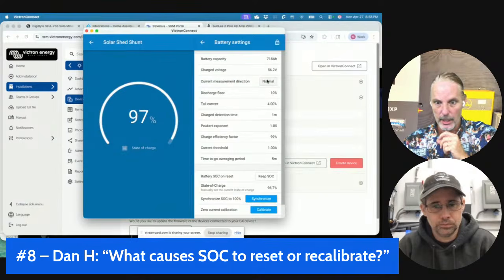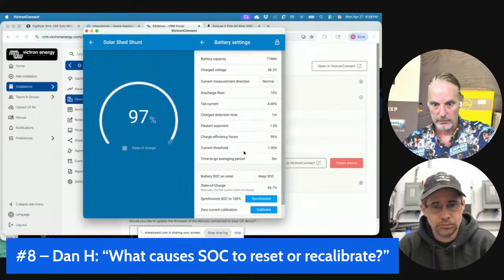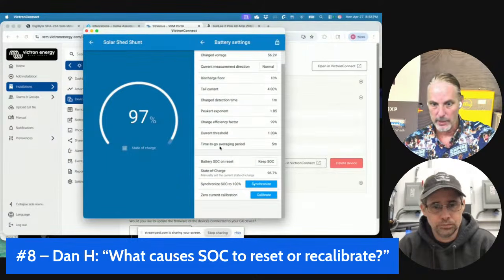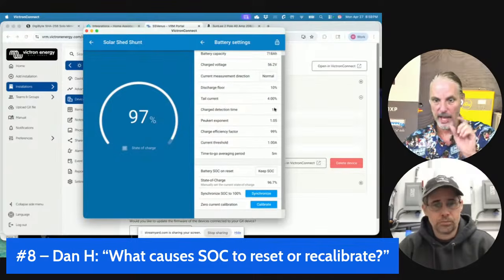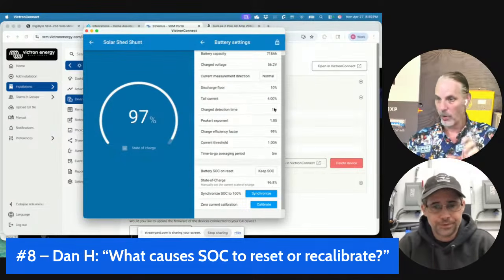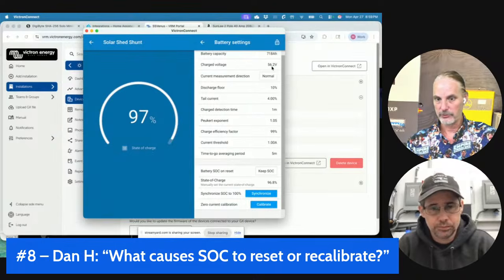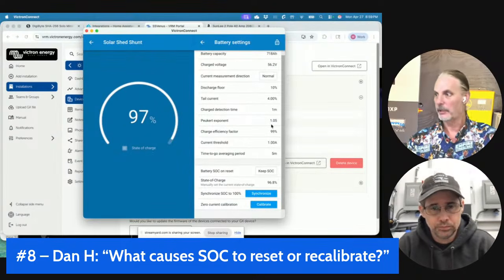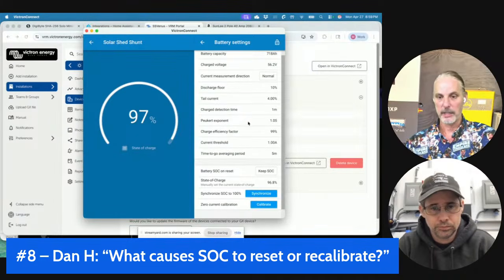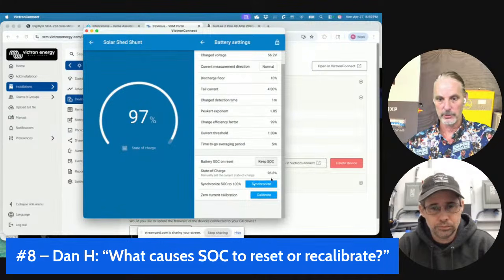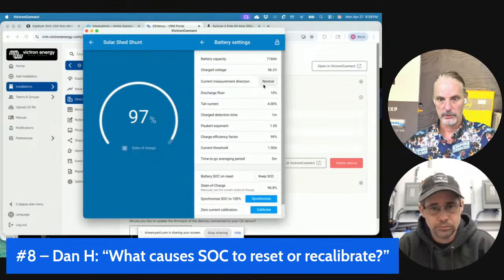All right, so let's look at what they call reset threshold: 1 amp. Charge detection time is 1 minute. So it has to be at less than 1 amp above the charge voltage, which is 56.2, for 1 minute. That's when it considers it a full charge, and it will drop to absorption time, which in my case will maintain 56.2 for... I don't know what I've got it set to.